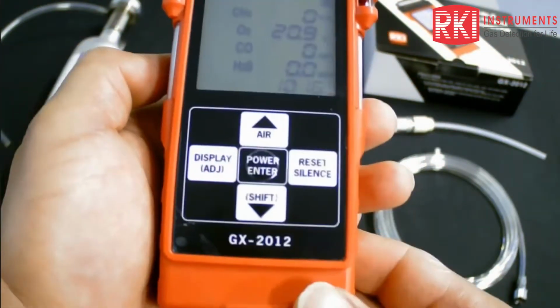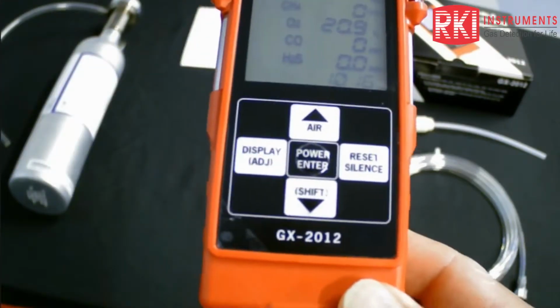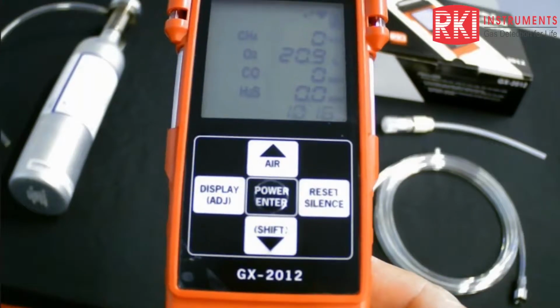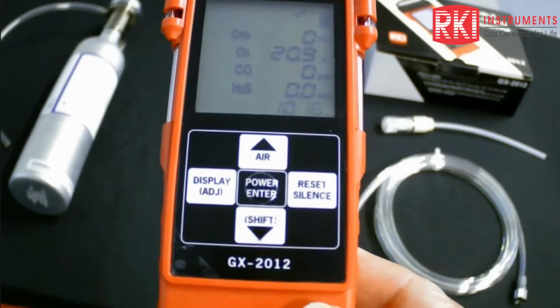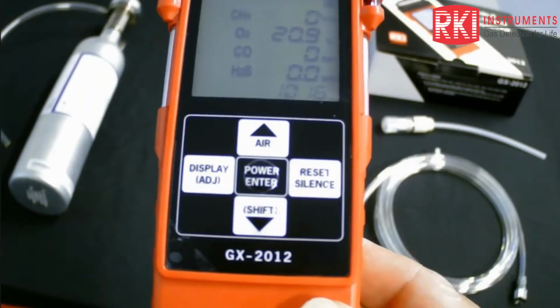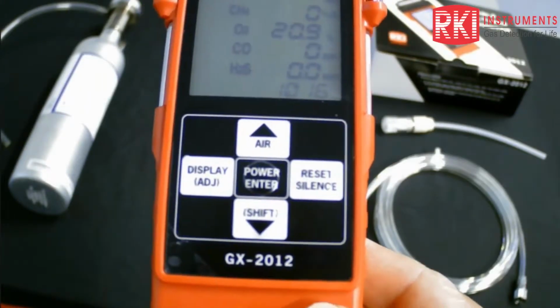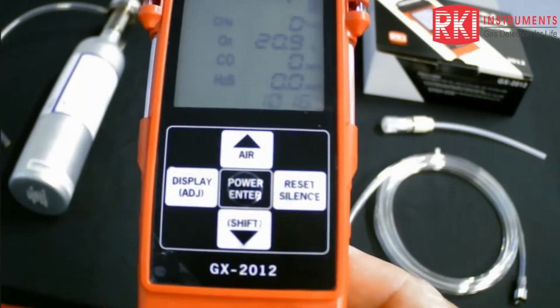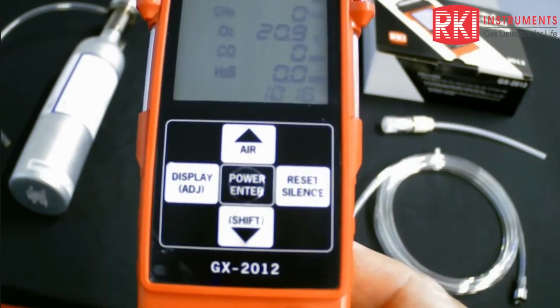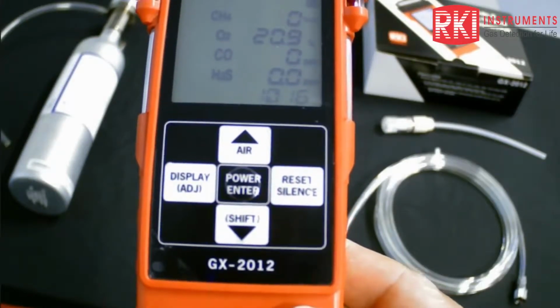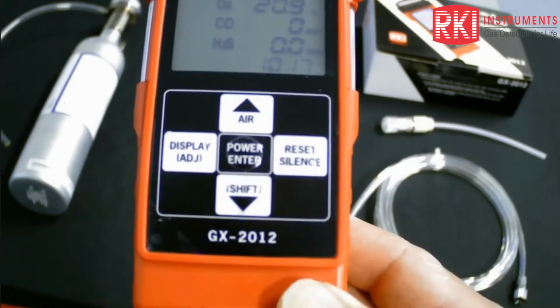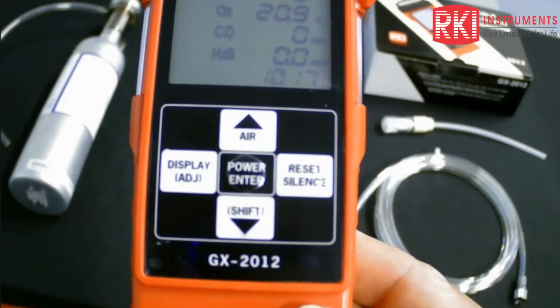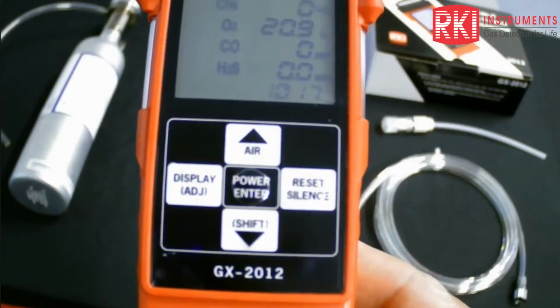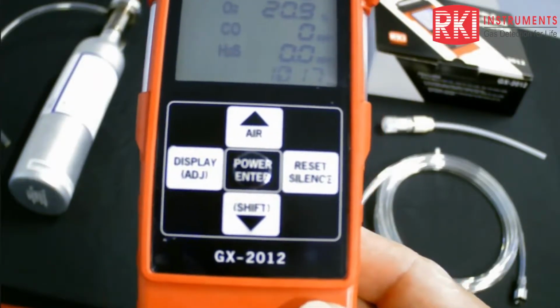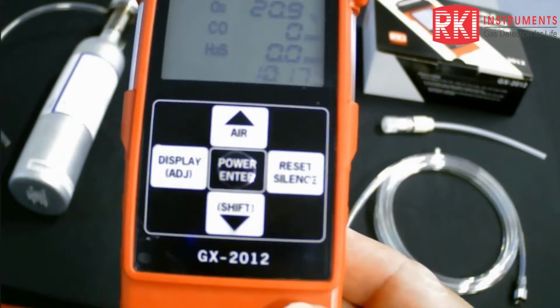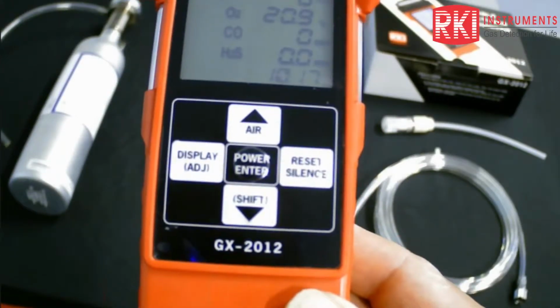One important point is if you are in an application where you expect to see a lot of gas, possibly right off the bat, then you would probably be well served to put the instrument into percent by volume only, turn off that catalytic sensor right away, therefore saving even more of its life. Because again, when it sees a lot of gas, that LEL sensor is going to range up to 100% LEL before it turns off. So you are taking it up to full scale before it turns off anyway. If you anticipate a lot of gas, put it in percent by volume, activate that TC sensor, turn off the catalytic initially, and you'll save even more life for it. And I'll show you how to do that as well.